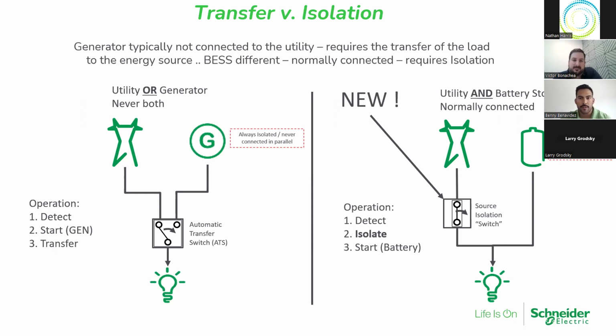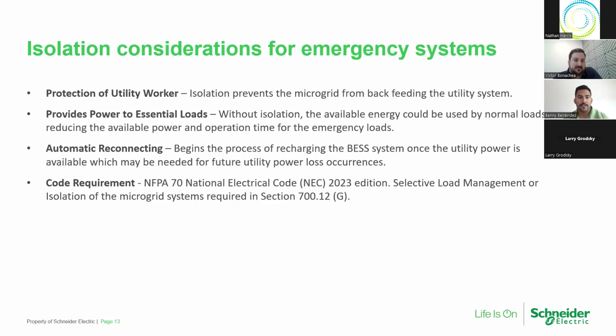Yeah, good points, Victor. So, isolation considerations for emergency systems. I think the primary one we're thinking about for safety is to prevent any backfeed to the utility system. To Victor's point, when we lose utility power or that primary power source, the inverters inherently shut down. The reason they shut down is in the event that you can't create isolation, you're preventing any backfeed up to the workers that are helping fix or bring back utility power.